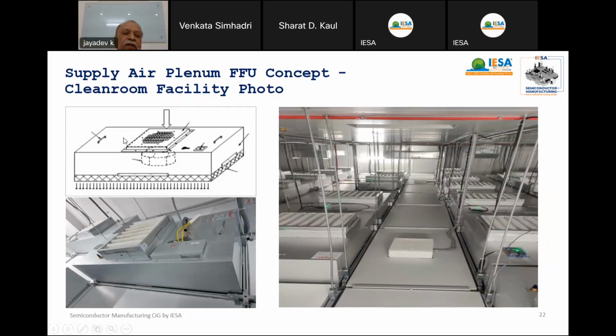How does it look? This is a fan filter unit, and this is the photo taken at the site. And there is a pre-filter for this. It is about 275 mm depth, 600 by 1200 mm. Inside, the filter dimension is almost equal to this, whereas the glass wool, glass media, may be about 58 to 60 mm thickness. So you can see the cloud of FFUs used in a class 1000 clean room. This is an actual picture taken at the site.